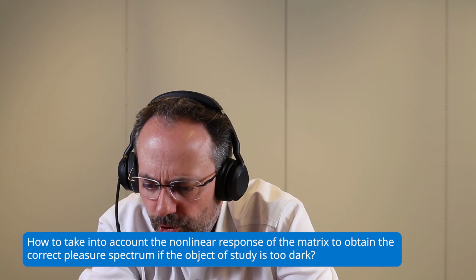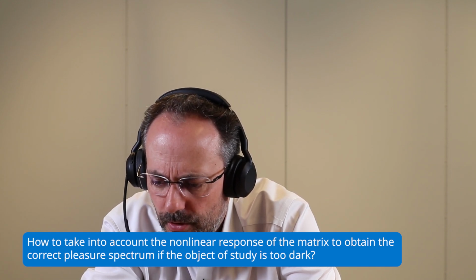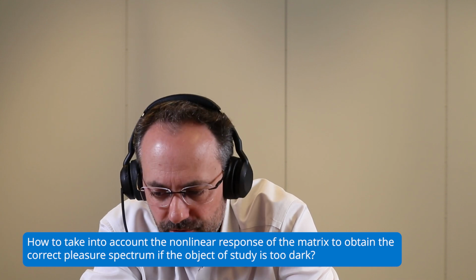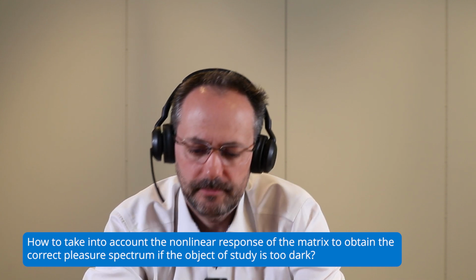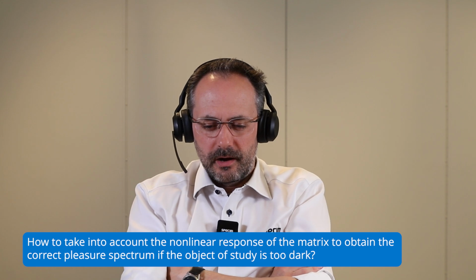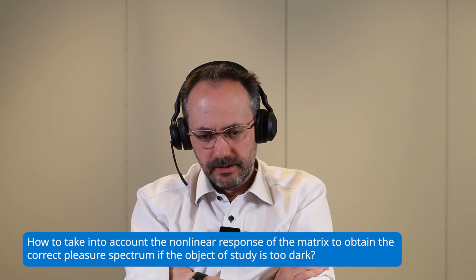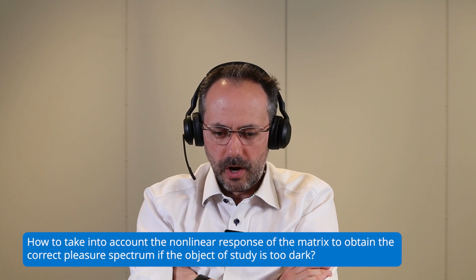How to take into account the nonlinear response of the matrix to obtain the correct spectrum if the object of study is too dark? Here, if we measure a dark object, I would actually recommend using 2 approaches. Instead of using a white reference, I would recommend using a gray reference. So instead of having a reference tile which is reflecting the light at 100% over the full spectral range, you can get another one which is at 50%, 70% or 30%. It depends on the one you want to buy.